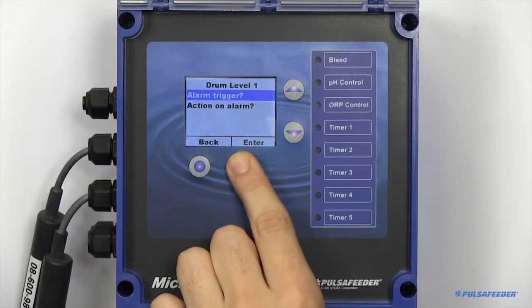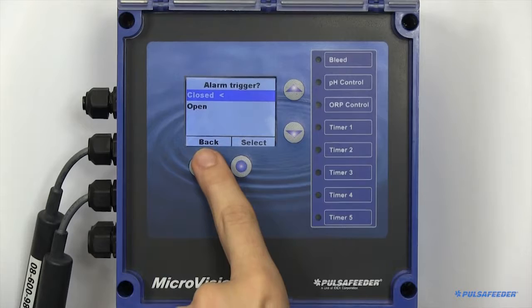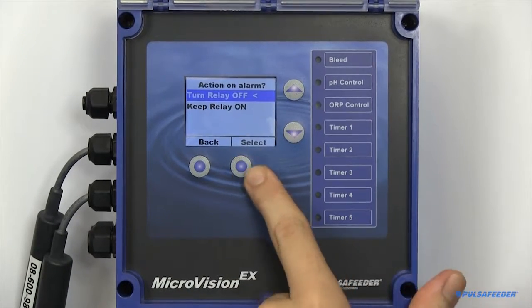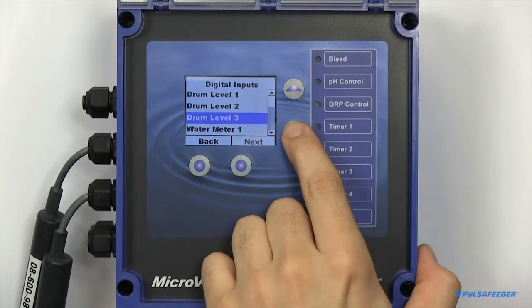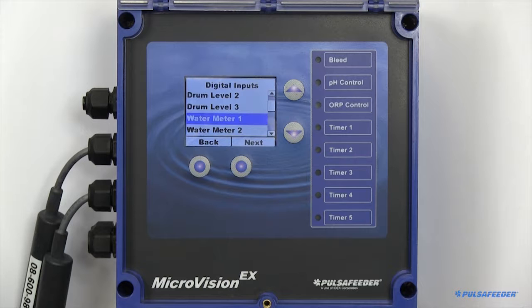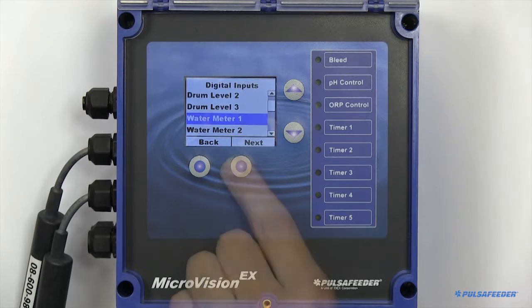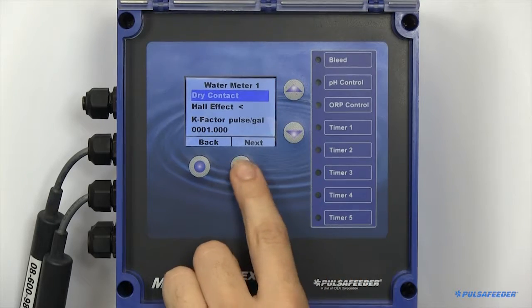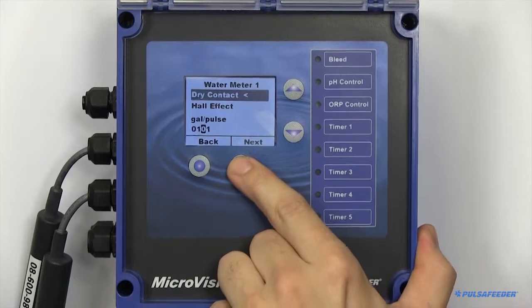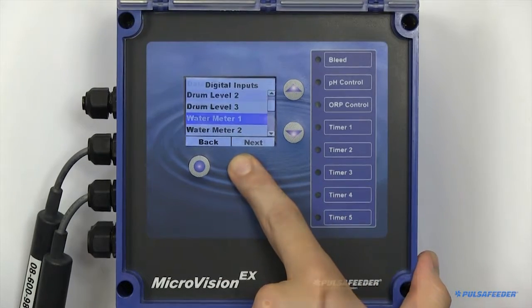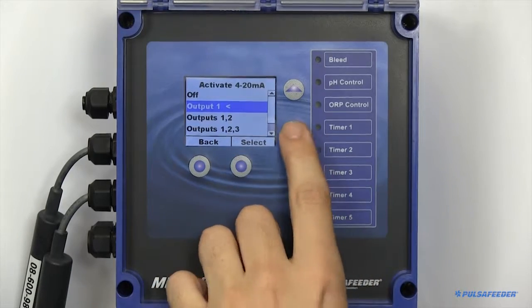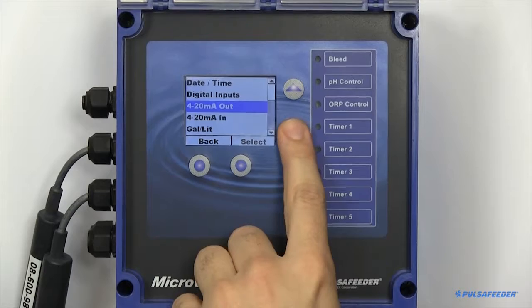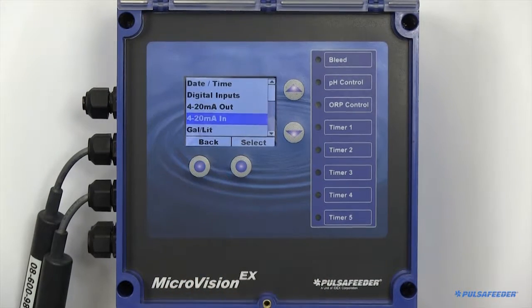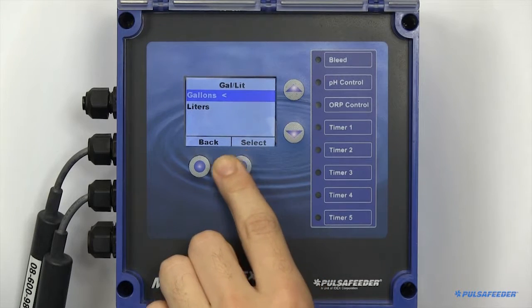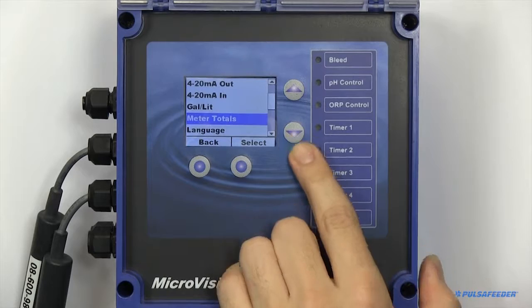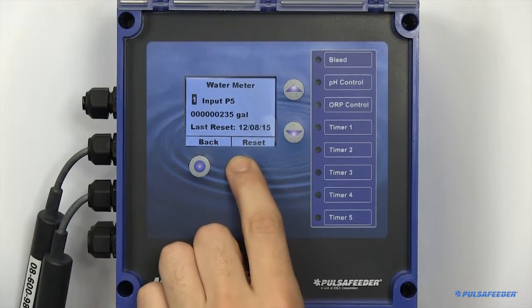Drum level sensors can either be configured to open or closed logic, and alarms can also be configured dynamically. Water meters can either be set up as a dry contact type or a Hall effect water meter. Each have their own independent multiplier. The 4 to 20 milliamp out and input functionalities are enabled and disabled here. The unit can either be configured in gallons or liters. Here is where you can reset any of your water meter values.